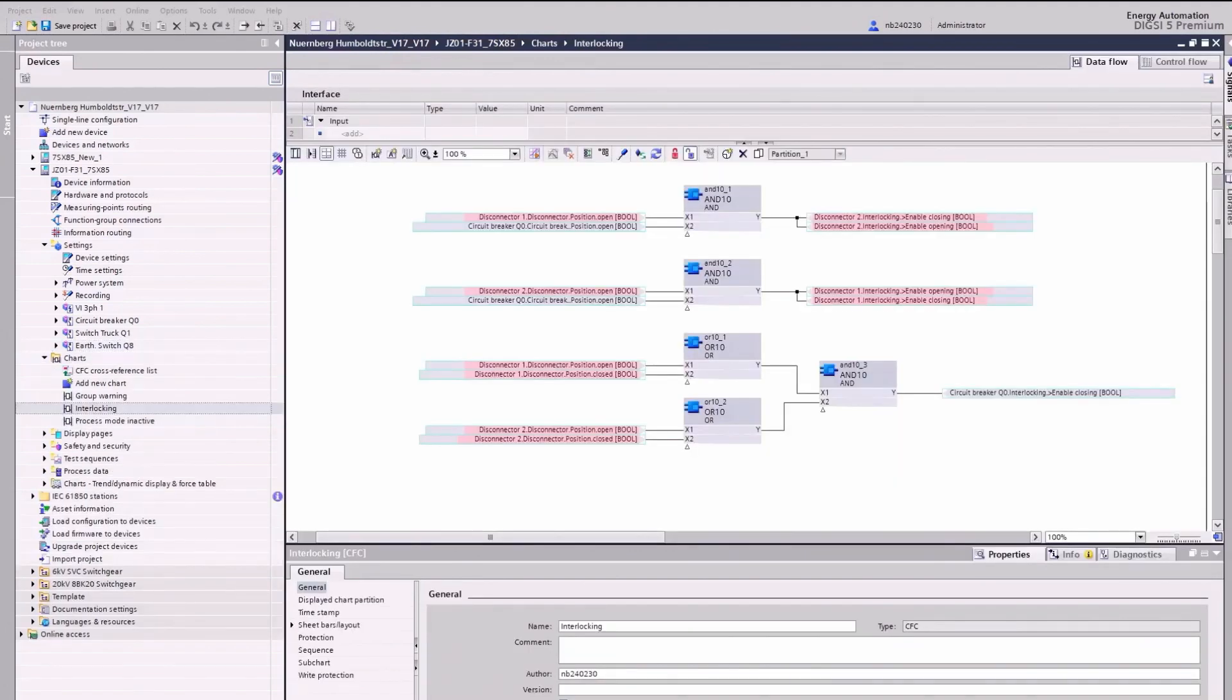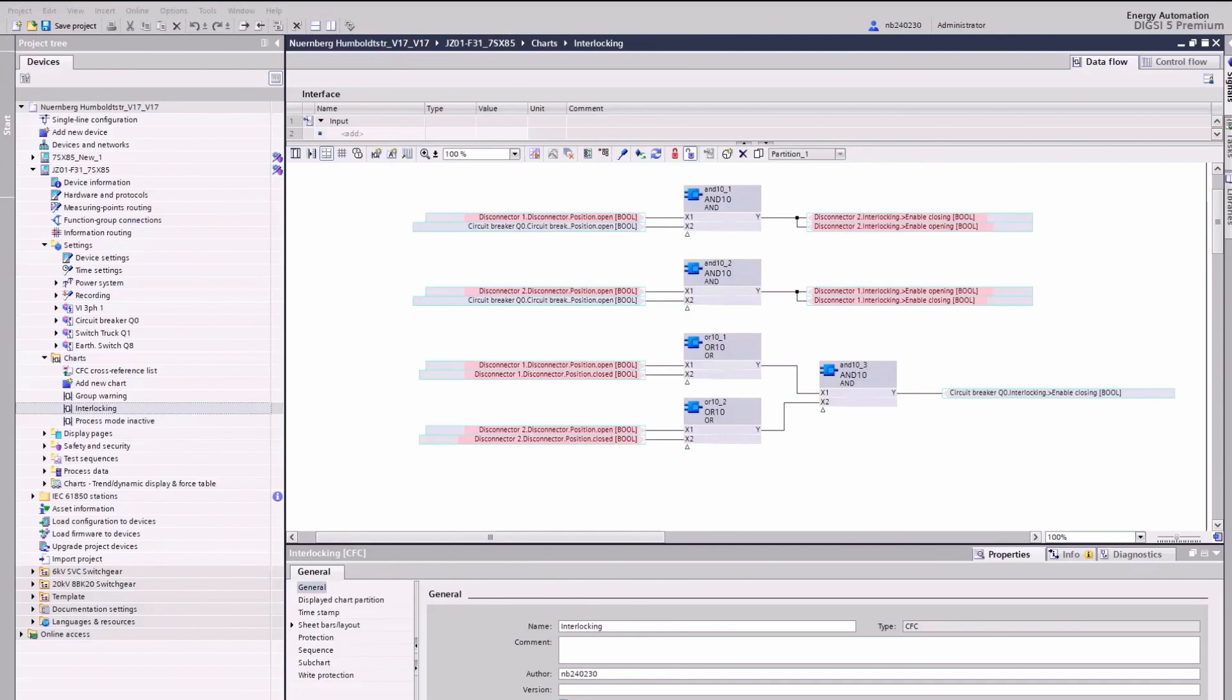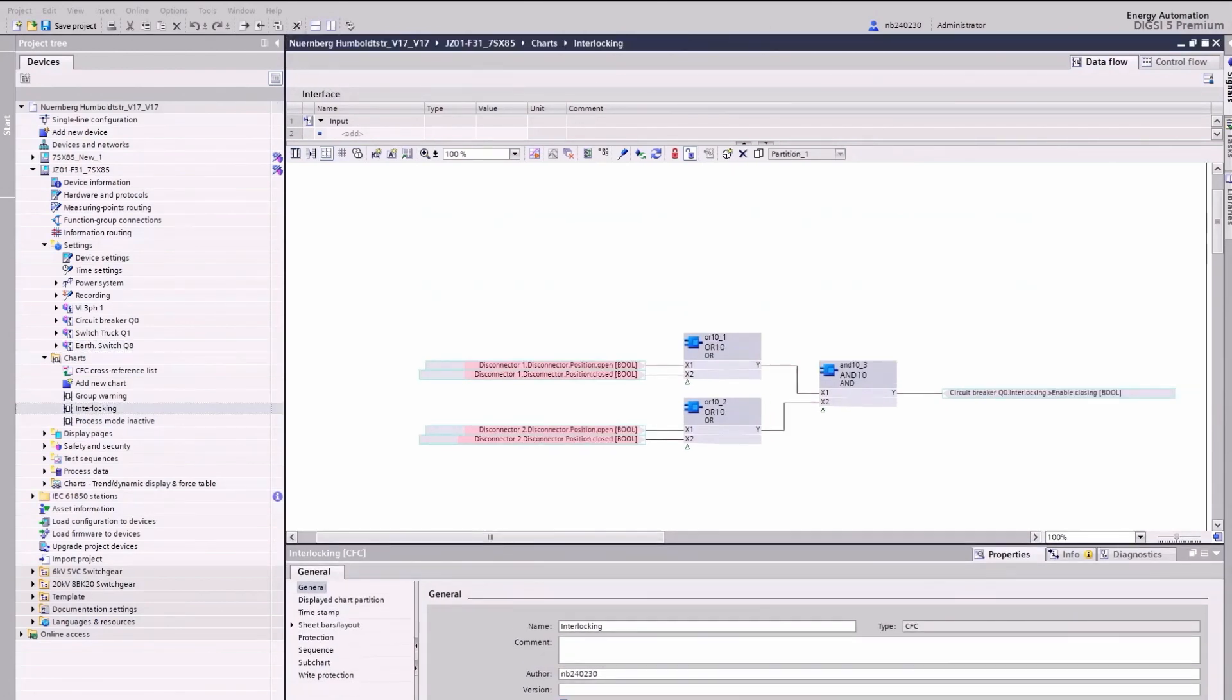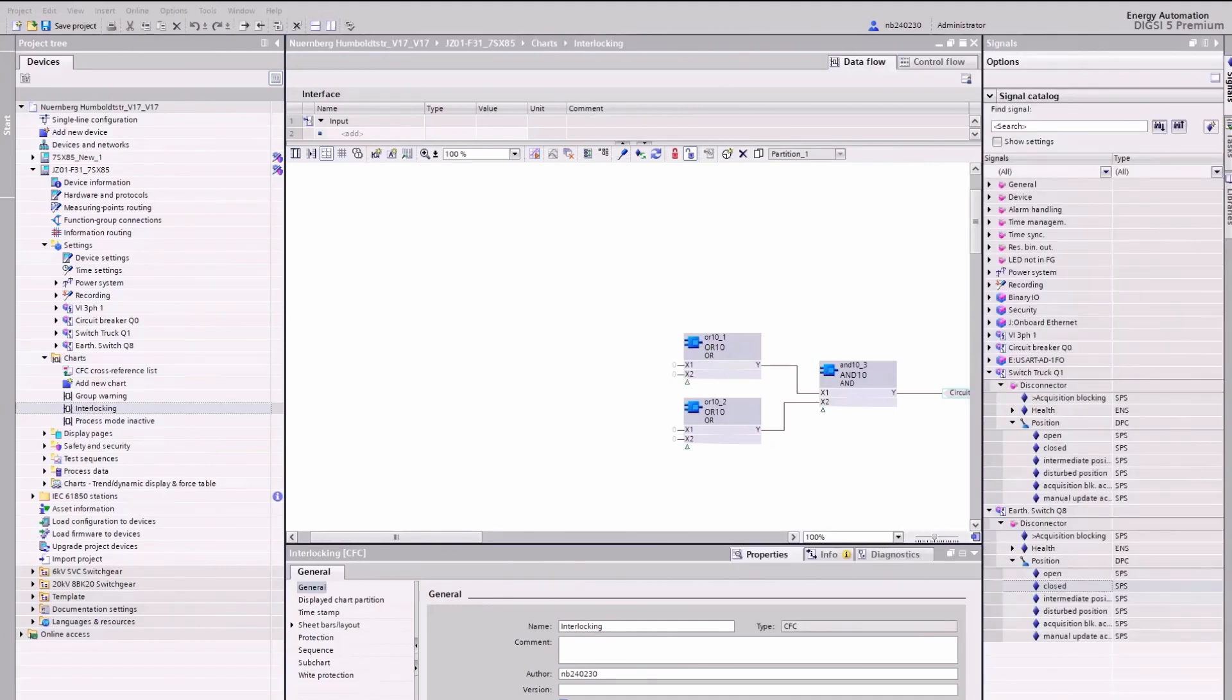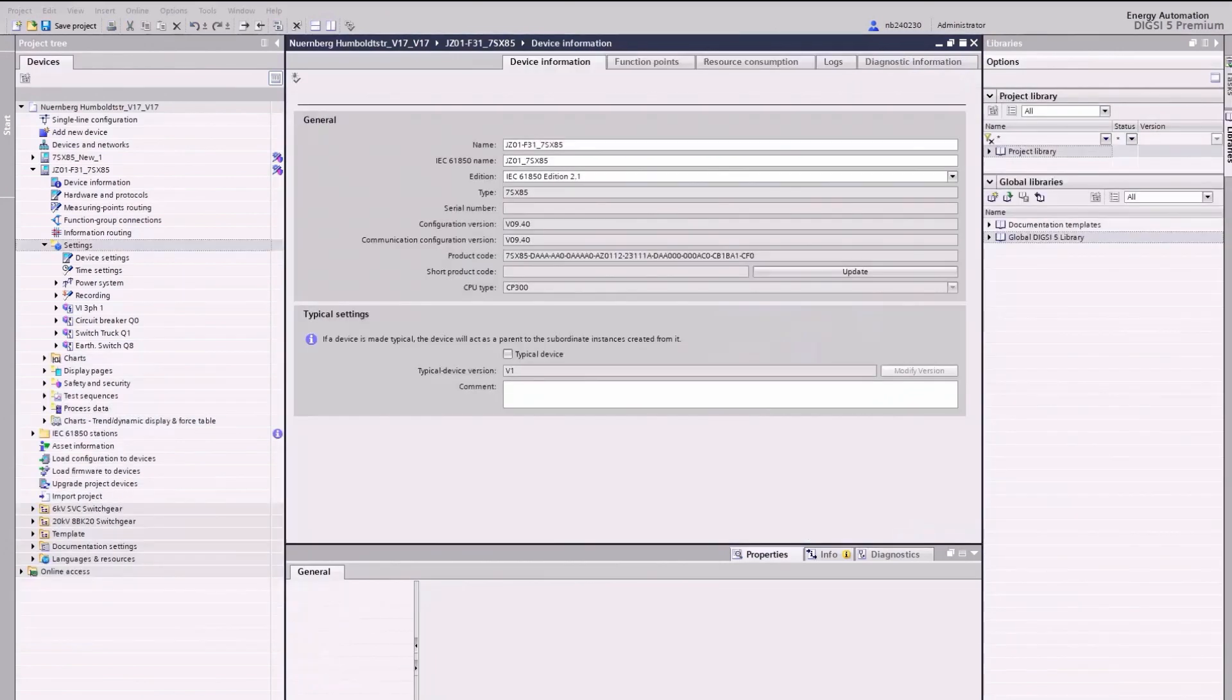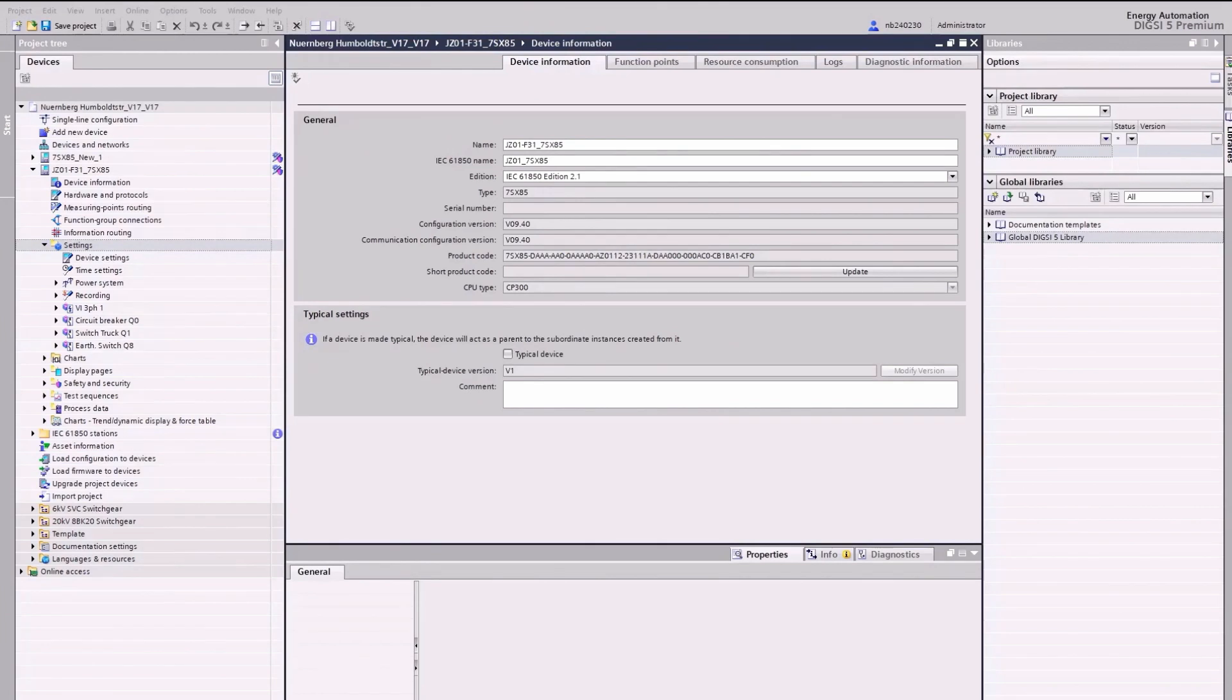With the change of switching devices from controllable to status only, we must adjust the pre-configured interlocking conditions. The switch truck Q1 and earthing switch Q8 are not controllable. We can delete the logic blocks for their interlocking conditions. And for the circuit breaker, we make a new signal connection. Now, we have prepared the 7SX85 protection device so that the range of function corresponds to that of the 7SJ641 device.